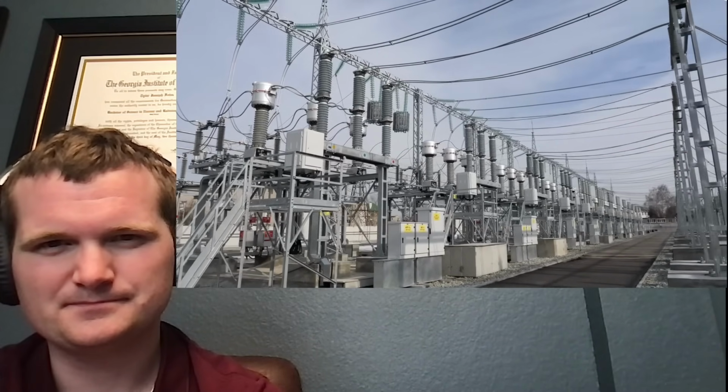Most folks have seen the breakers that protect circuits in your house. The electrical grid has similar equipment used to protect transmission lines and transformers in the event of a short circuit or fault. But unlike the breakers in your house that do both the sensing for trouble and the circuit breaking all in one device, those roles are separate on the grid. The physical disconnecting of a circuit under load is done by large, motor-controlled contactors quenched in oil or dielectric gas to prevent the formation of arcs.